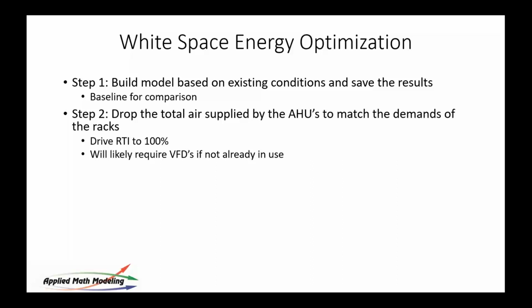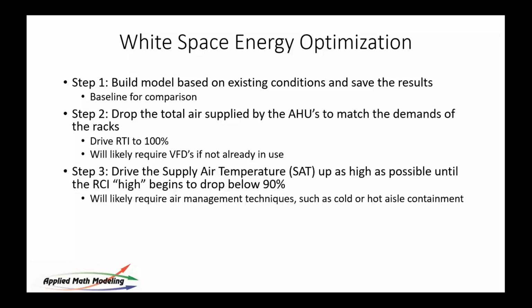And so VFDs are popular to try to get that closer to 100. The next step you do is to drive the supply air temperature up as high as possible until the RCI high, which is the metric. Again, I'm referring back to DCEP training.